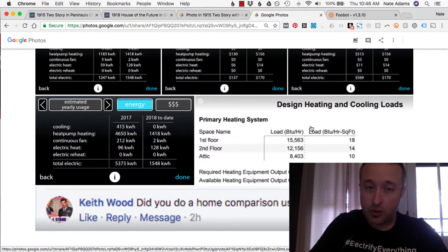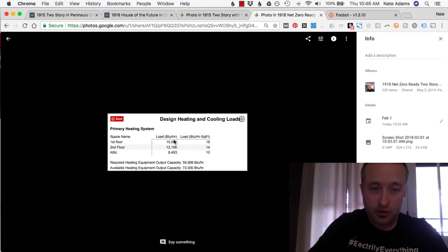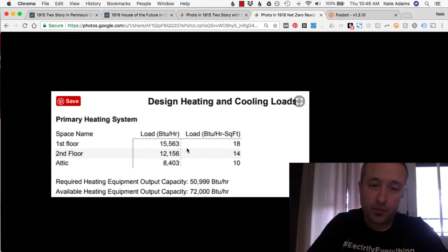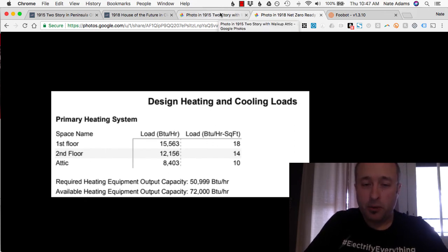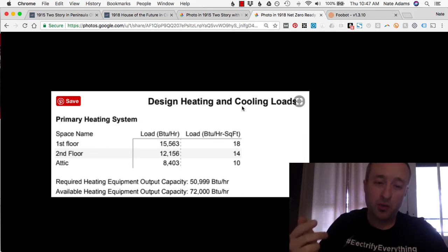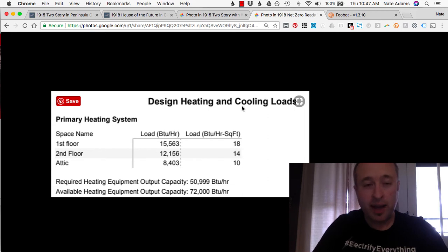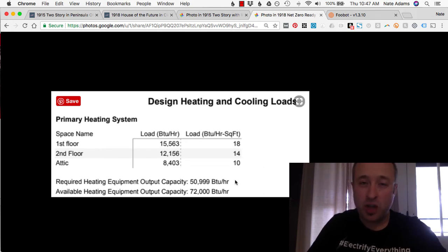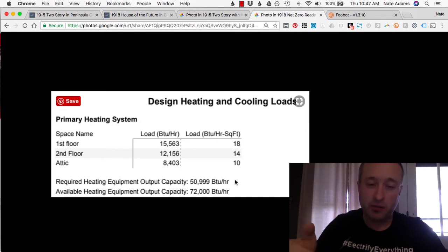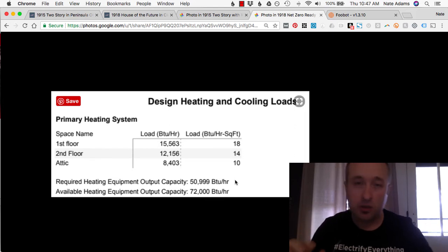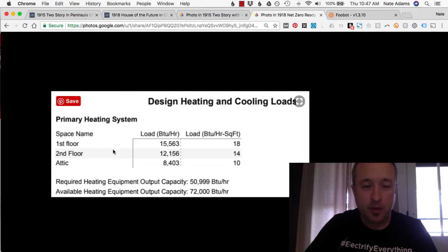Now the last thing that I want to touch on is heating and cooling loads, because these houses are fairly different in this. Fairly different, but pretty similar at the same time. So this is what's called heating and cooling loads. This is how much, through a program that we use, it says it's going to take to heat or cool a given house. There's a couple of numbers you want to look at. This required heating equipment output capacity is what's called a Manual J. It's not exactly a Manual J because it's calculated in a slightly different way, but it's close. And a Manual J is an industry standard load calculation, something that's used really consistently. At this house, it's about 51,000 BTUs. You can see this is how much it takes to heat or cool the individual floors of this house.